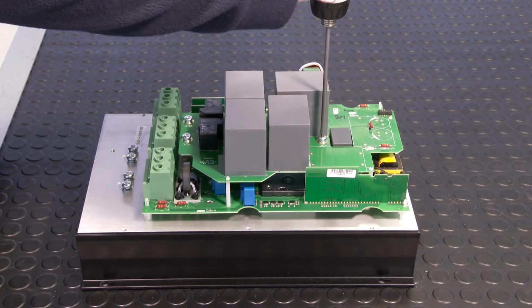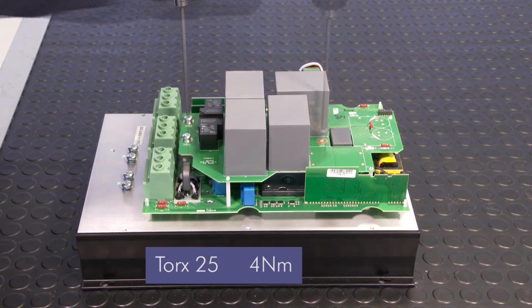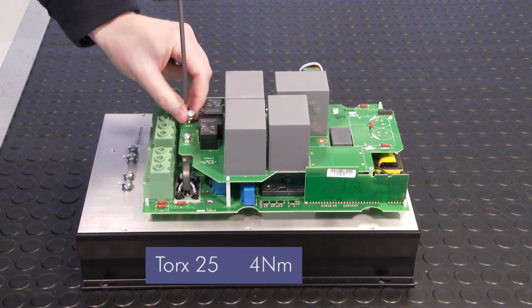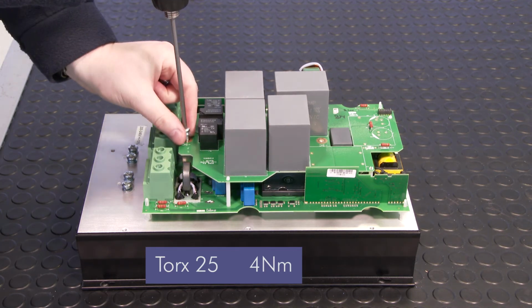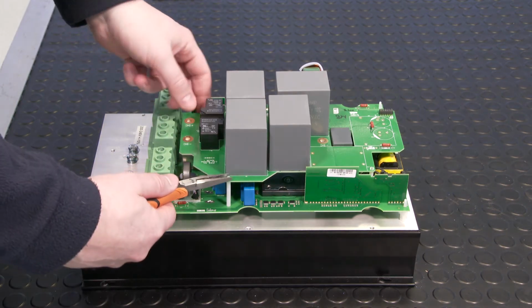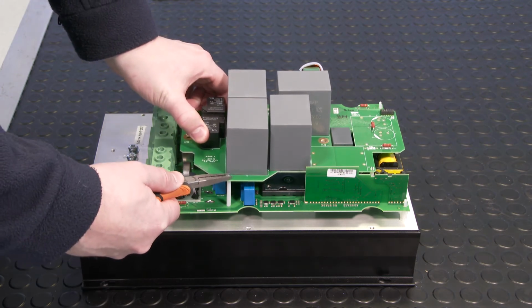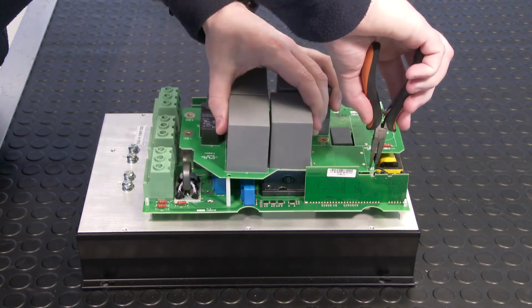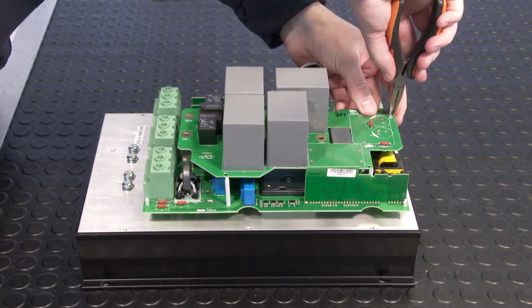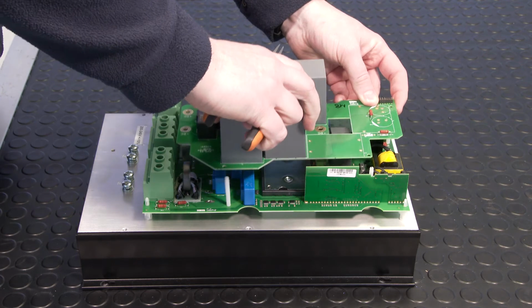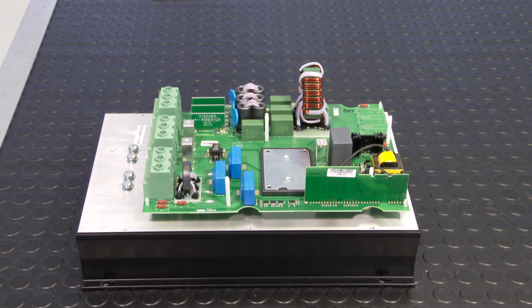To remove the DC capacitor board, use a Torx 25 screwdriver to remove the 3 screws. The torque setting is 4 Nm. Using long nose pliers, unclip the 4 plastic pillars from the PCB and lift it away. Replace the DC capacitor board using the parts supplied in the preventive maintenance kit when rebuilding the drive.